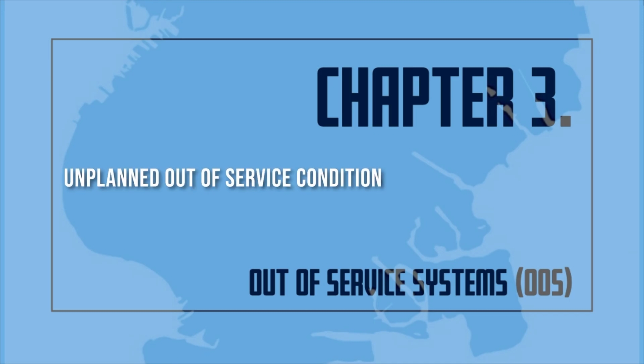Unplanned out-of-service condition. Any person, upon becoming aware of any condition, except a planned removal from service, rendering a standpipe system, sprinkler system, or fire alarm system, or part thereof, inoperable in whole or in part, shall notify the owner and the impairment coordinator of such condition. The impairment coordinator shall take the actions as required by the code, and such other actions as are necessary or appropriate to protect the occupants of the building and promptly restore the system to service.